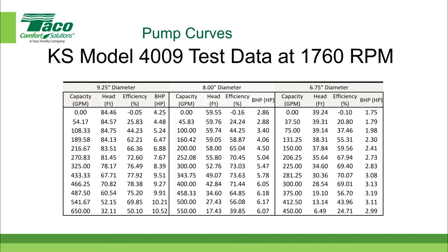He continues collecting data for the 9.25-inch diameter impeller. Then at the end of that test, he dismantles the pump, removes the 9.25-inch impeller, and installs an 8-inch diameter impeller, repeating the process all over again. Then he does it a third time, installing a 6.75-inch diameter impeller, repeating the data collection. So he uses this information to collect data for three distinct impeller diameters.